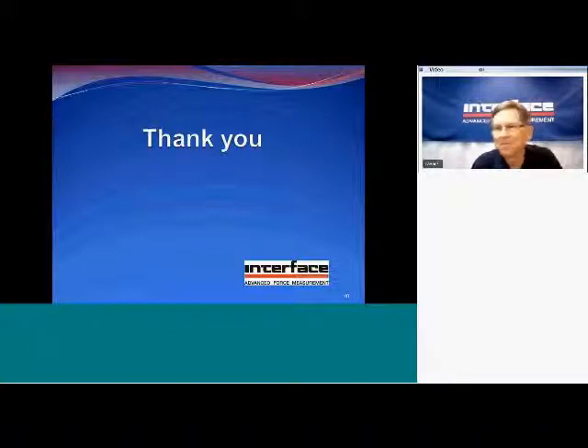So let's move on. Does Interface provide the owner of its calibration system with an uncertainty value? The answer is that in general, no, but we provide help. The uncertainty belongs to the laboratory. So only the operator of the laboratory knows his calibration intervals, his temperature controls, and other parameters that affect the uncertainty. So we give some help as provided in this webinar, but no, we do not give a guaranteed number.